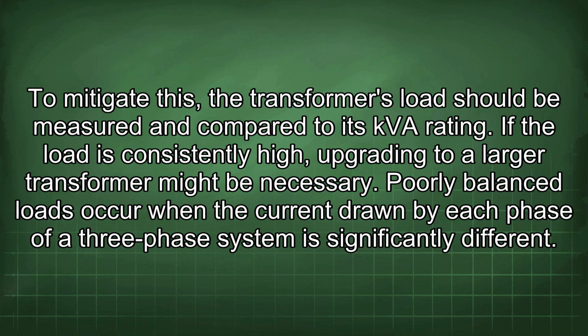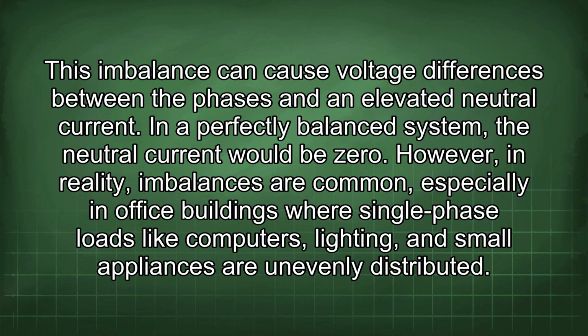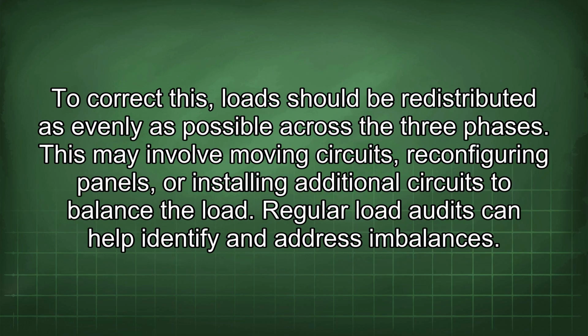Poorly balanced loads occur when the current drawn by each phase of a three-phase system is significantly different. This imbalance can cause voltage differences between the phases and an elevated neutral current. In a perfectly balanced system, the neutral current would be zero. However, in reality, imbalances are common, especially in office buildings where single-phase loads like computers, lighting, and small appliances are unevenly distributed. To correct this, load should be redistributed as evenly as possible across the three phases. This may involve moving circuits, reconfiguring panels, or installing additional circuits to balance the load. Regular load audits can help identify and address imbalances.